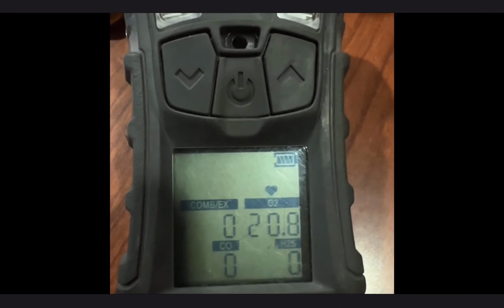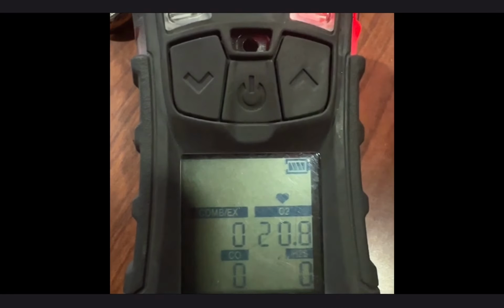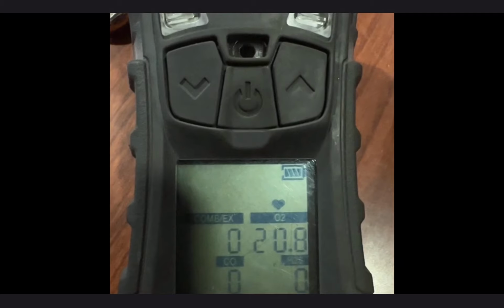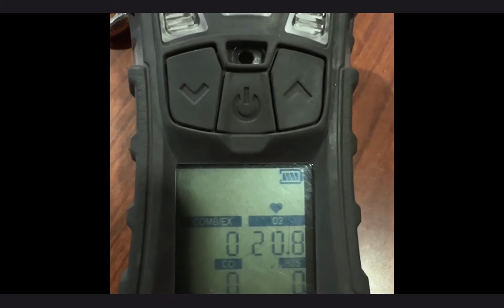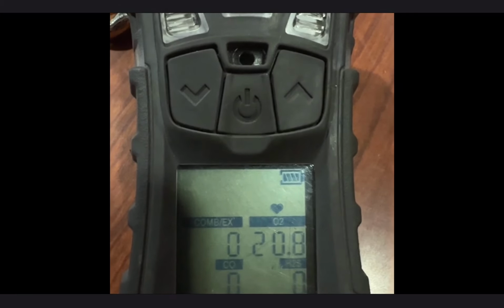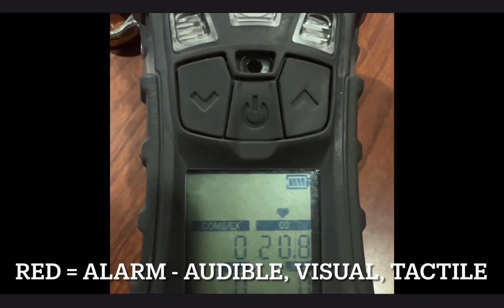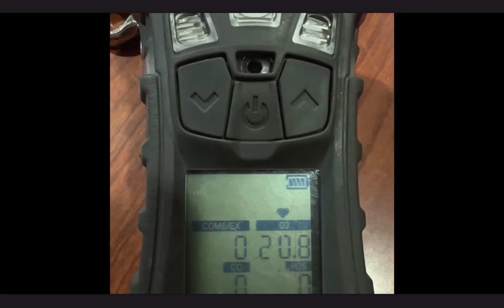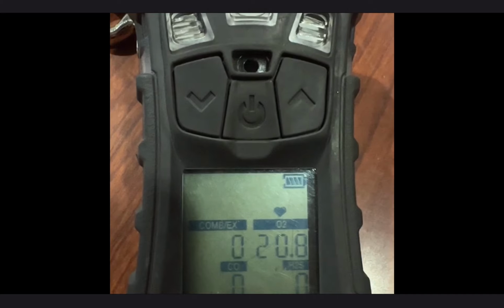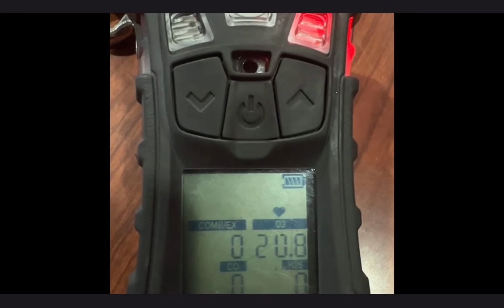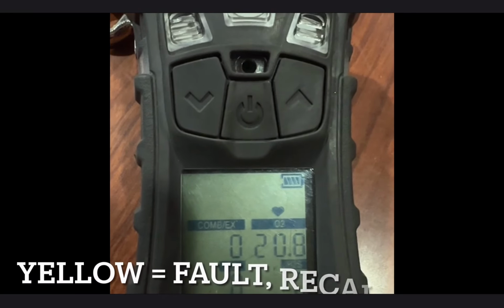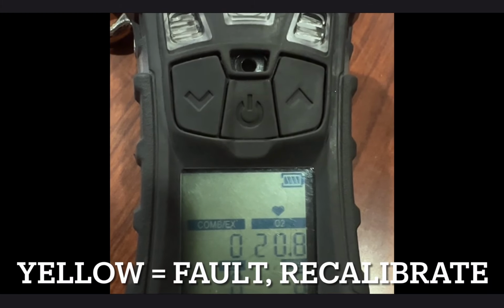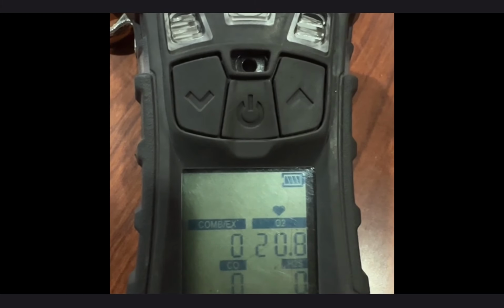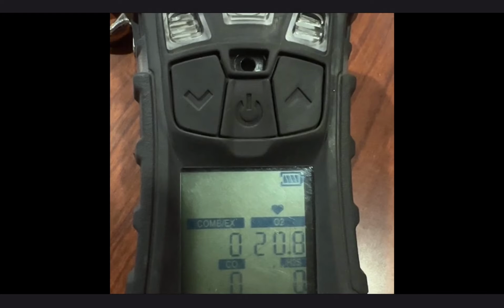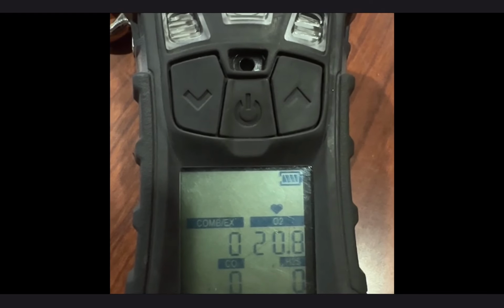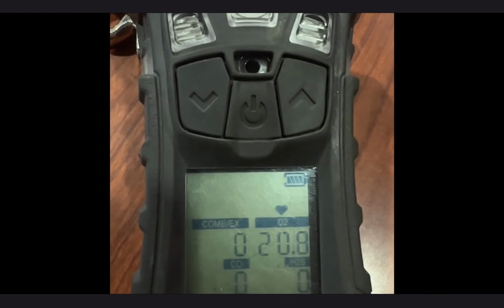So these monitors, going back, and it's the same for the new one and the old one, they have 3 different light indicators. Red, which means it's either charging or it's alarming. When it alarms, you have a visual, the red light going off, the vibration, and also the audible noises going off. Yellow means there's a fault of some kind. You could get that during charging, during calibrating. And if you were to get a fault, try to recalibrate again, start from the beginning. And if you get it again, then that monitor's out of service.